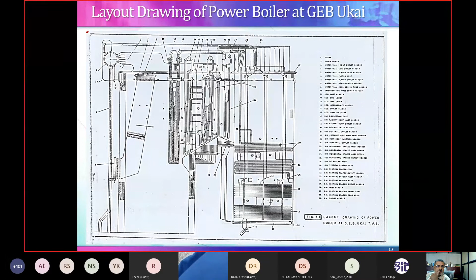Now, what results did we get? After these trials as per BS 2885, the auxiliary power, that is all your ID fans, FD fans, and the feed pump, reduced from 111.56 to 109.33 megawatt hour per shift. There's a 2% reduction. Boiler efficiency improved from 82.99 to 85.64, so a 3.19% improvement. Overall generation efficiency improved by 2.5%. Overall plant efficiency improved by 2.65%.